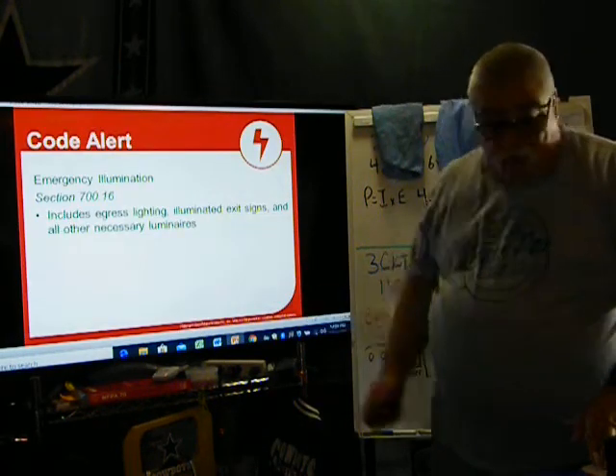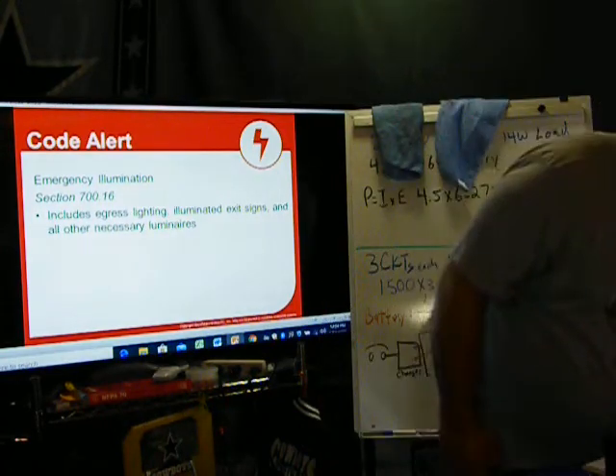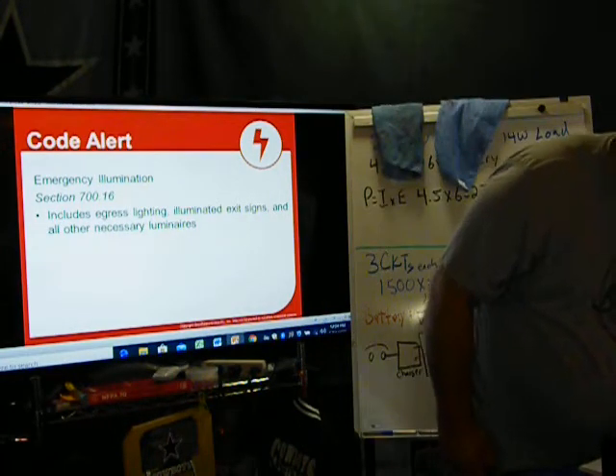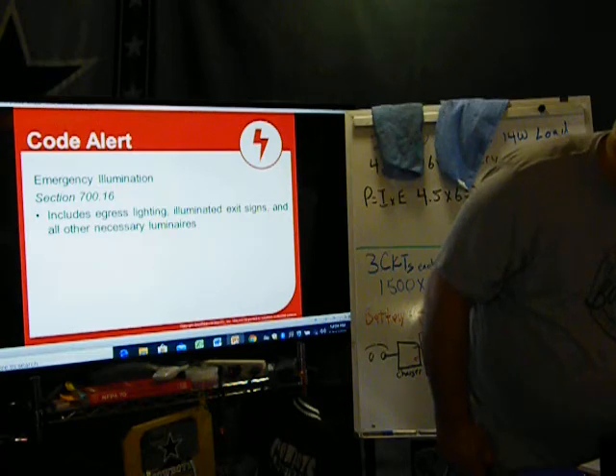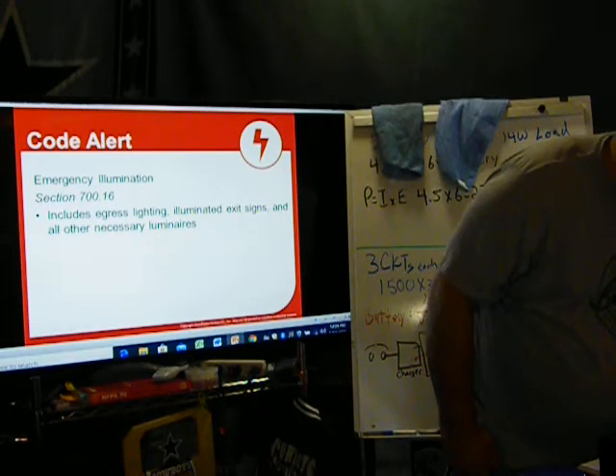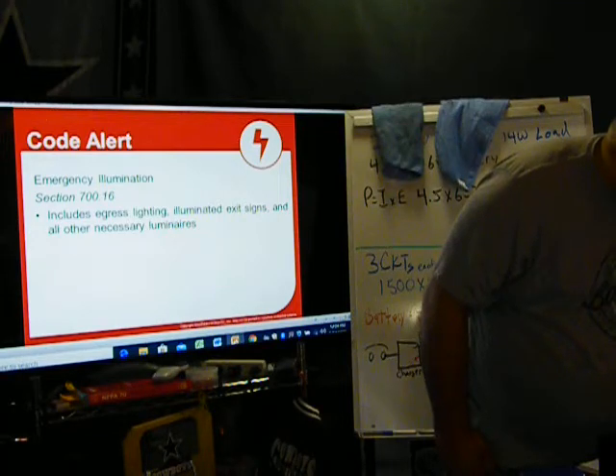Emergency illumination, I was talking about the 716, that was the code. It says, according to section 716, emergency illumination shall include all required means of egress lighting, illuminated exit signs, and all other luminaires specified as necessary to provide the required illumination. Okay.